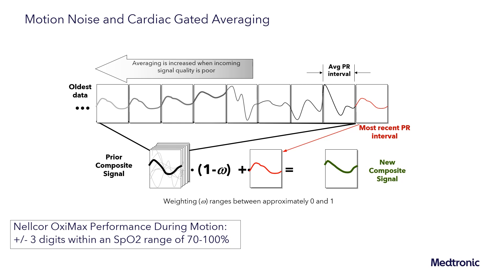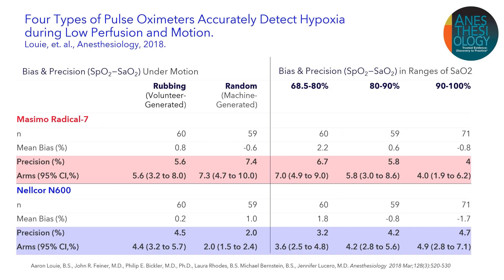That composite signal, because it averages these prior signals, can scrub out that noise and decrease it such that the new composite signal — built up from the prior signals — is reflective of that true patient pulse. Utilizing this method of cardiac gated averaging, again putting an emphasis on the pulse from the patient, and able to scrub out that noise, Nellcor is able to achieve motion performance of plus or minus three digits from that SpO2 range of 70 to 100%. We can see this play out in the literature. Here is a study looking at various pulse oximeters and their performance under both low perfusion and motion — a challenging situation for the pulse oximeter to work under. All of the system has to work in unison here to be able to achieve that performance.